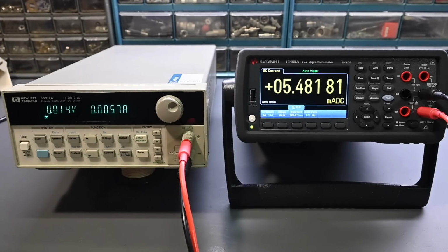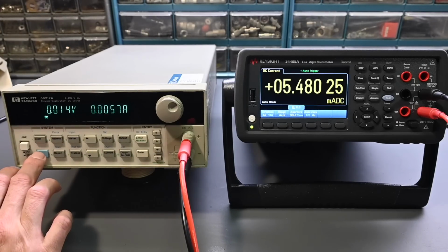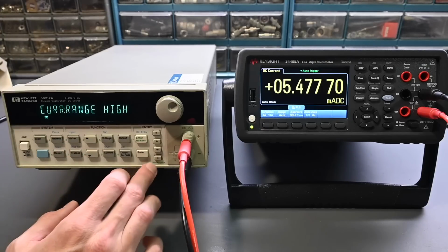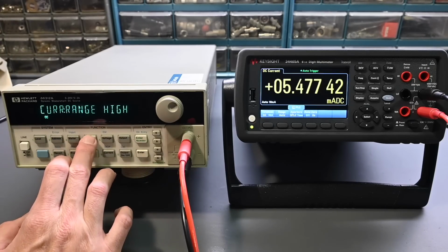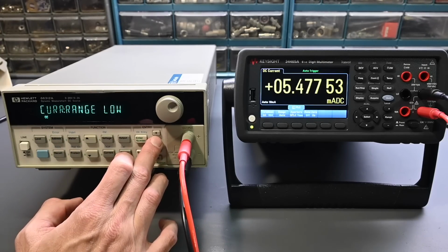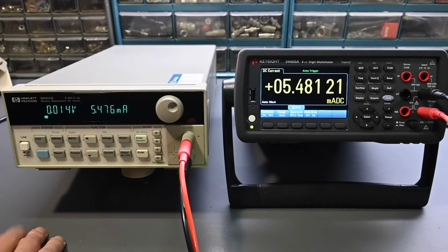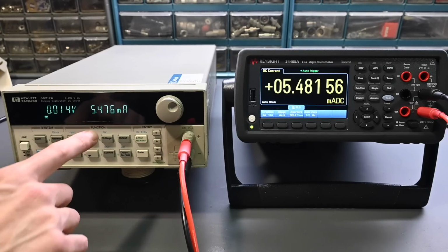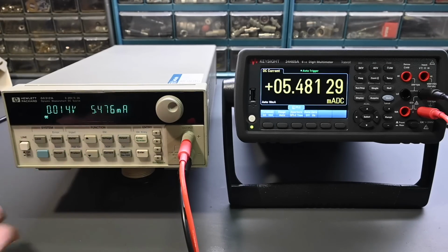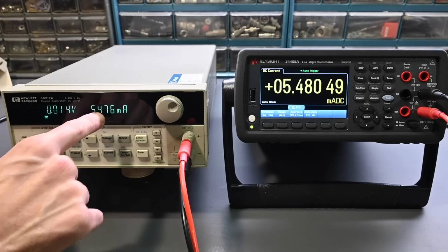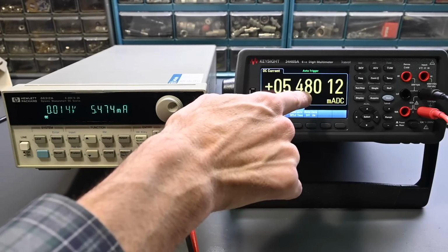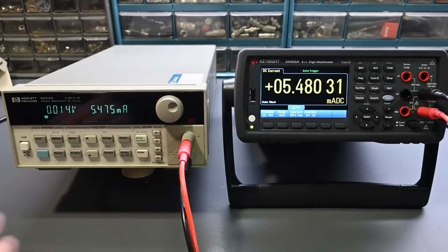We should be able to measure current even lower than that. If I go to this input, current range, what do I do right here? Low current range, let's try that. So now this is reading in milliamps. So you have milliamps, a decimal point, and then microamps. So 5.476, 5.47, yeah, really close. Really, really close. That looks good. Very happy with those results.